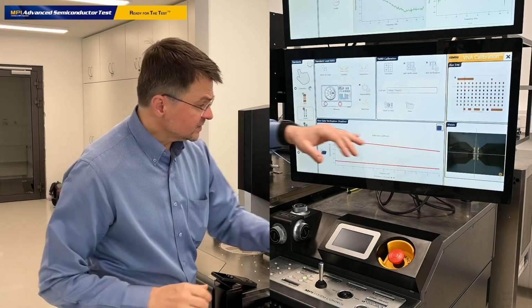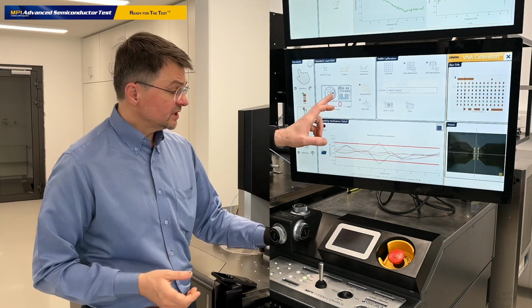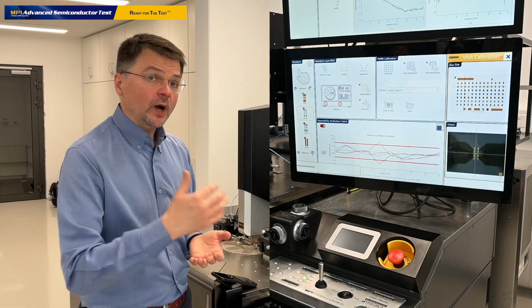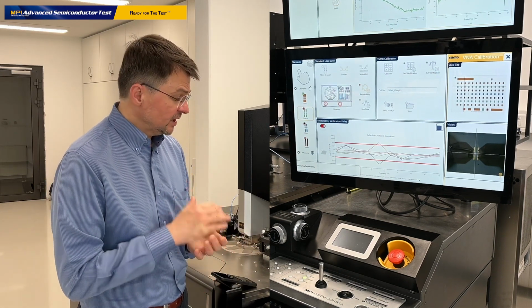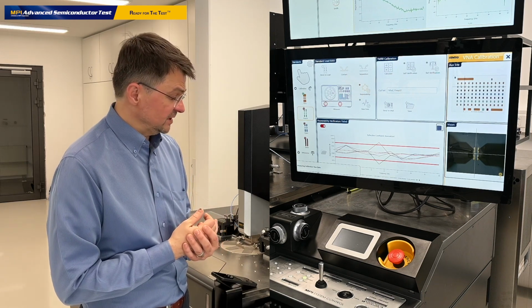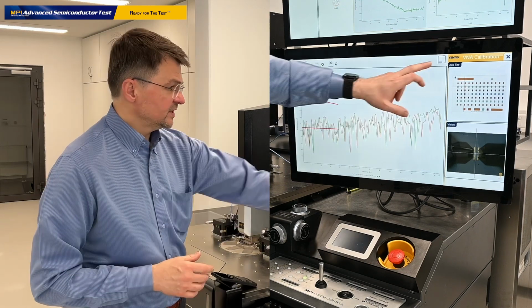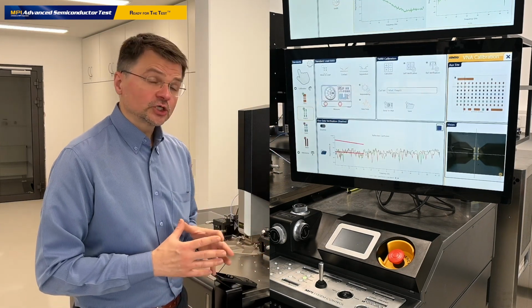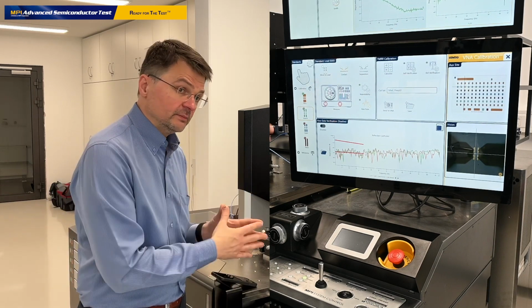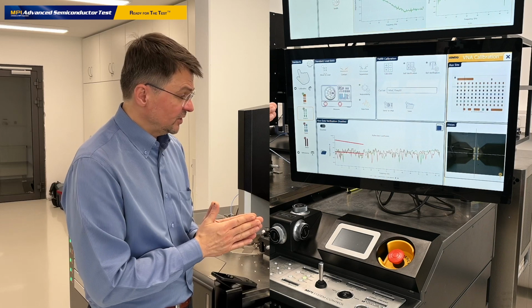Well, we are in contact. We can acquire measurement data. Let us wait a little bit. So we trigger the measurements, and Calibria will acquire the data on the load standard, checking repeatability first, and then measuring the raw data. What we can see is that the repeatability data passed. It's a very good example where I can show you how to adjust the boundaries for the pass and fail criteria on the particular calibration standard.